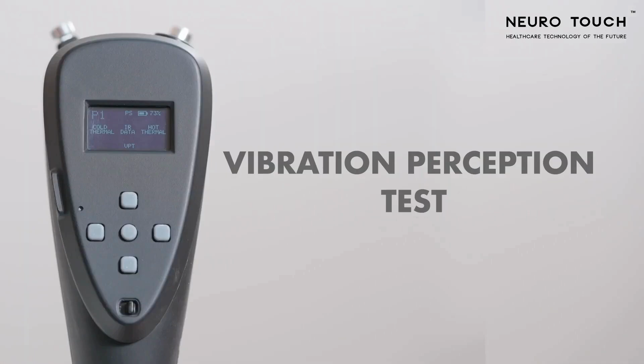Vibration perception test. Click the bottom key to start the vibration perception test. To perform the vibration perception test, set the voltage to 10 volts by clicking the up arrow key. You can use 10 volts as the starting value for all 12 test points. Place the vibration probe against the patient's test point.